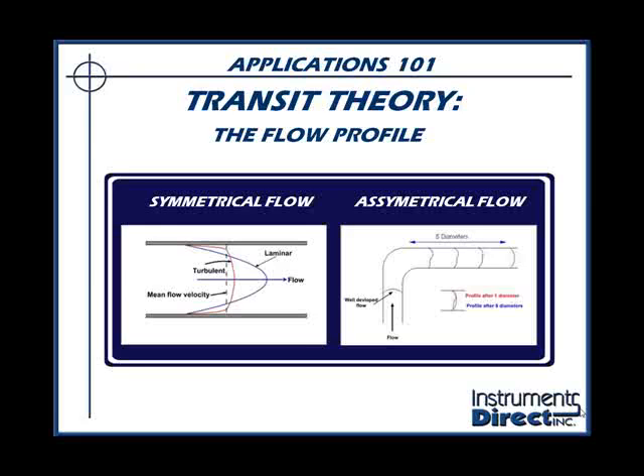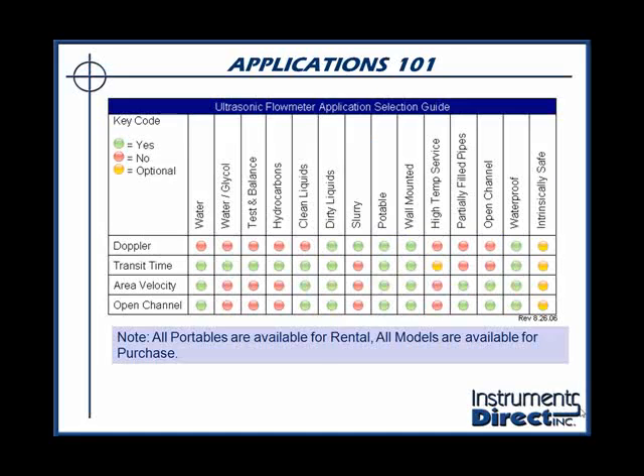It'll work on an ultra pure liquid up to applications that are about 4 to 5% solids by volume. A generic description of that would be ultra pure liquid to sewage, but it does not work on sludge. Don't confuse an ultrasonic transit time flow meter with an ultrasonic Doppler flow meter. Doppler flow meters are traditionally used for heavy slurry applications, and that is covered under a different theory.